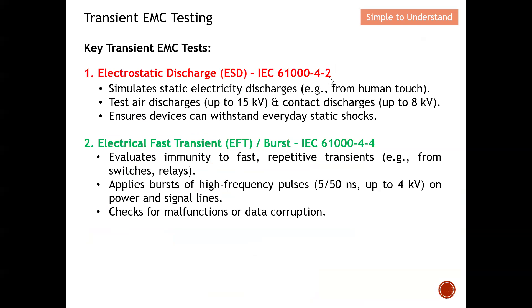I have already completed the discussion on electrostatic discharge, which is according to IEC 61000-4-2 standard. The reason we need to do this test is that every one of us has experienced a situation where we are about to touch a conductor and either discharge to it or it discharges to us, feeling a pain on our finger. We need to ensure that the device we manufacture can withstand this kind of static shock. When you touch your DUT you discharge a waveform to it, and the device must still be able to function. Essentially it simulates static electric discharge from a human to the device — there is a contact and non-contact method.